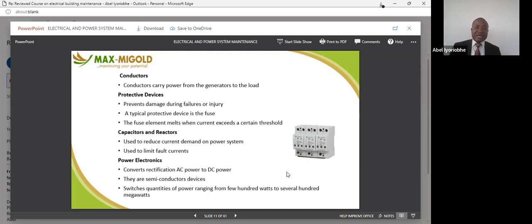But fuse has a very disadvantageous effect. Most people abuse fuse by putting wire and thinking that they have done well. They put oversized fuse and it doesn't serve as a protective device anymore. It only serves as a link. So when there is a problem, the fuse is meant to open or melt. Because the wire is overrated, it doesn't open anymore. What happens? It damages the equipment that it is meant to protect.